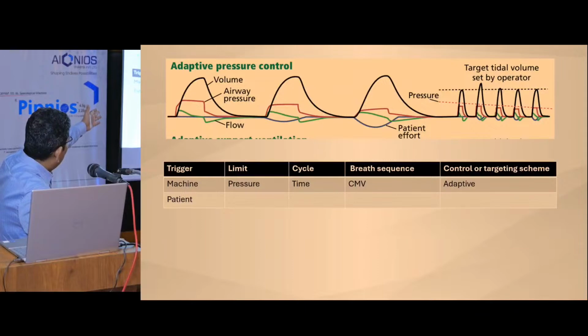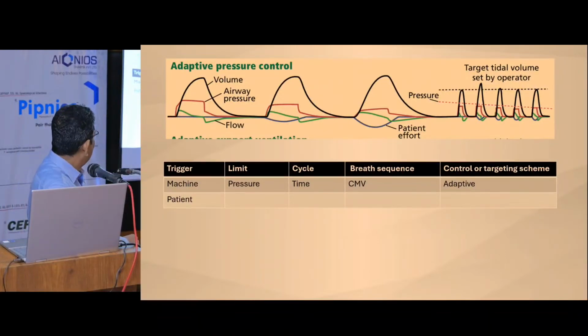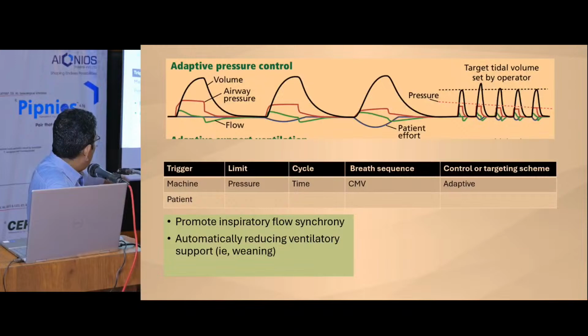So trigger, machine or the patient. Limit is pressure only here. Cycle again, time cycle like pressure control. Mandatory breath definitely, but the control one is adaptive. The ventilator adapts the support or changes the support, unlike a pressure control ventilator. Okay, fine. So it promotes inspiratory flow synchrony. Okay, very good at synchronizing with the patient, and automatically reduces ventilatory support as the patient starts breathing more.